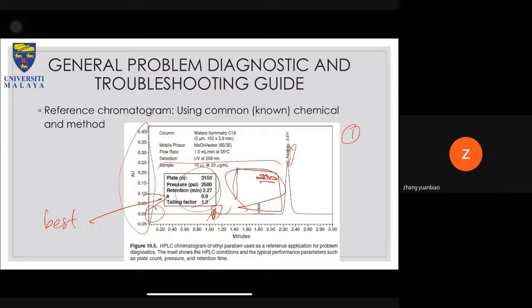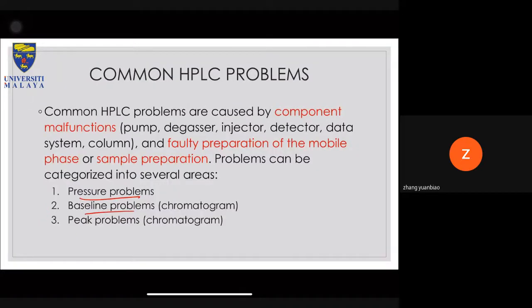Okay, so common HPLC problems are caused by component malfunction and faulty preparation of the mobile phase or sample preparation. Problems can be categorized into several areas, and these are the 3 highlighted areas that I've chosen. First is pressure problem, second is baseline problem, and number 3 is peak problem. Baseline problem and peak problem are related in the sense that both of them involve the chromatogram, but as you will see next, I will give more specific examples in each category.